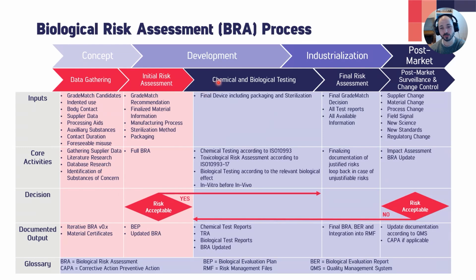So what you will do is chemical characterization according to ISO 10993-18. And then you will do a toxicological risk assessment. What you also usually do is the big three: cytotoxicity, irritation, and sensitization testing. With that, you would have a pretty good understanding of your device. Sometimes it's necessary to have even in vivo tests, which you would do in parallel. And when we have all this data gathered, we will put it into our final risk assessment, which is an updated version of the initial risk assessment. So all this data and all the learnings go into the initial risk assessment, and then we have the final risk assessment.